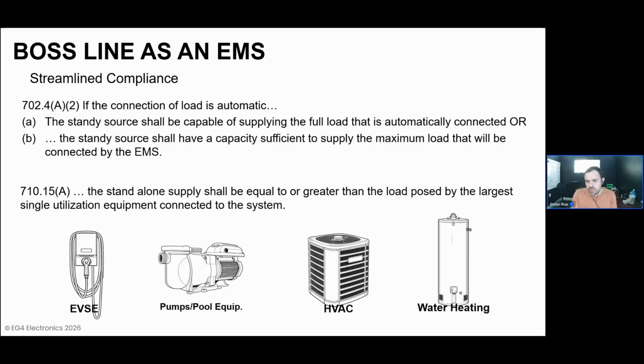Instead, what we can do with the GridBOSS is simply relocate that single largest load to one of our smart circuits. Again, we can support up to 125 amps with our largest smart circuit within the GridBOSS, and have that load be automatically shed when the grid is lost, thereby adhering to this section of code. So again, this really can streamline the compliance situation for niche conditions or abstract scenarios as those come about for our partners in the field.